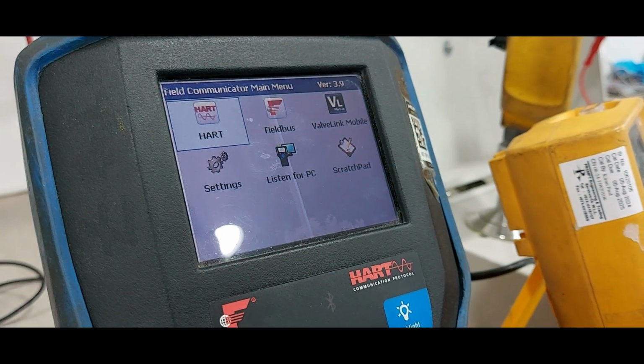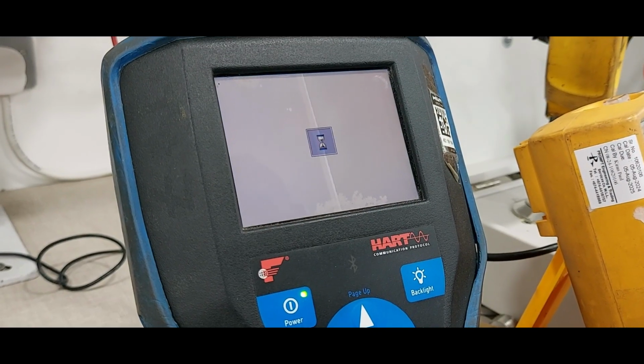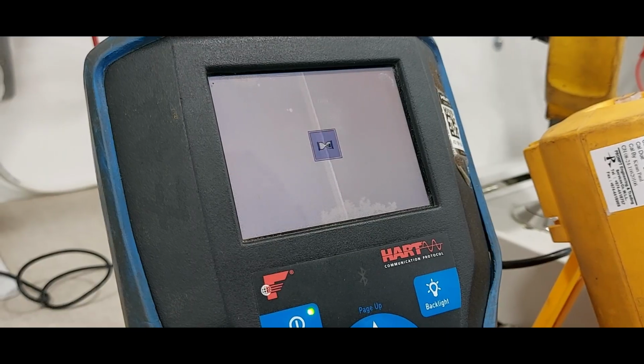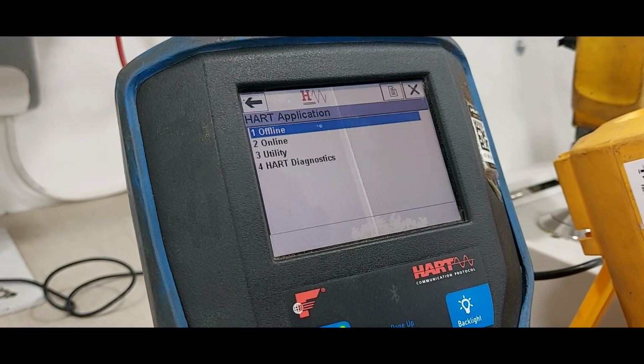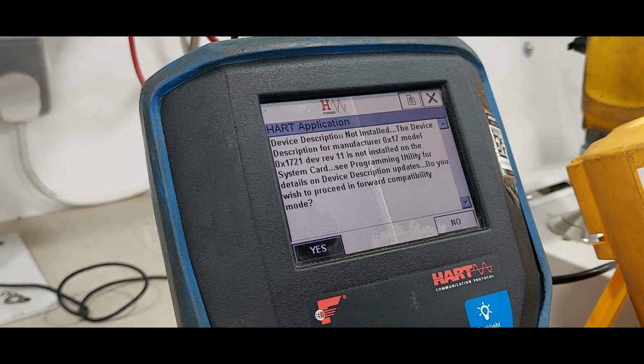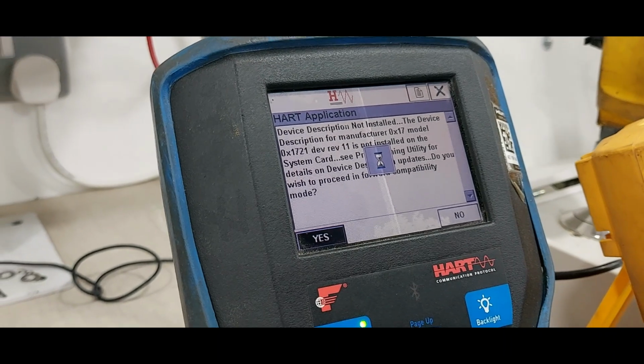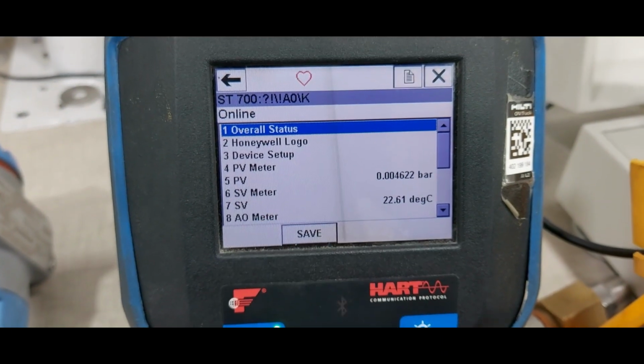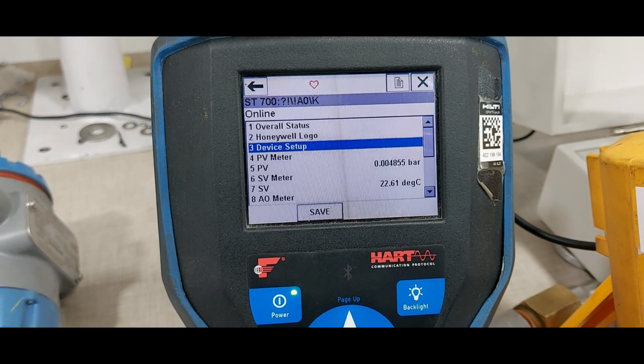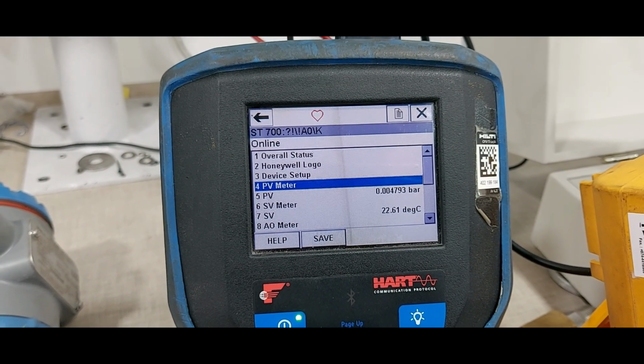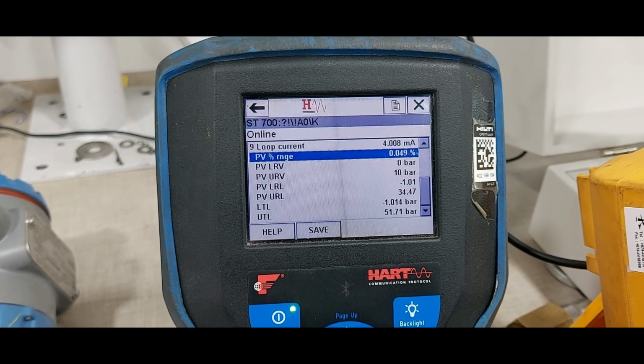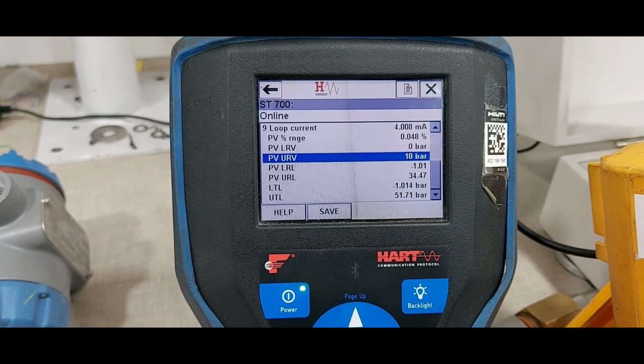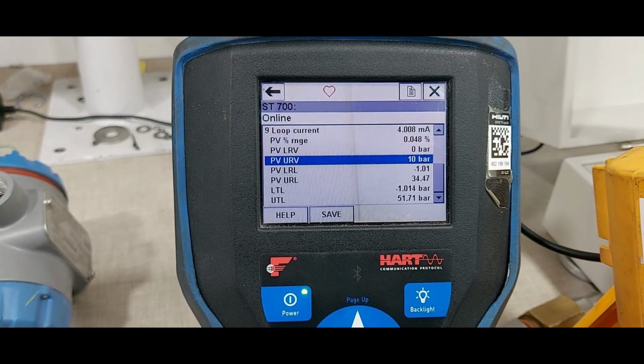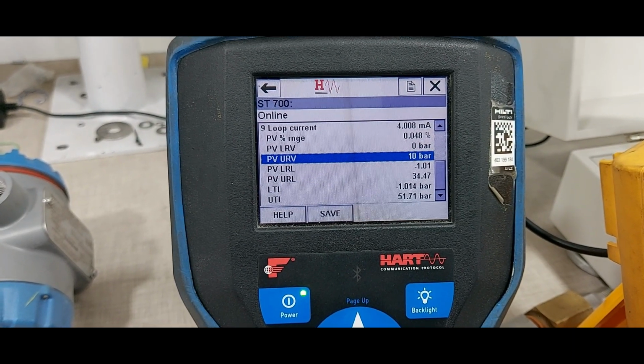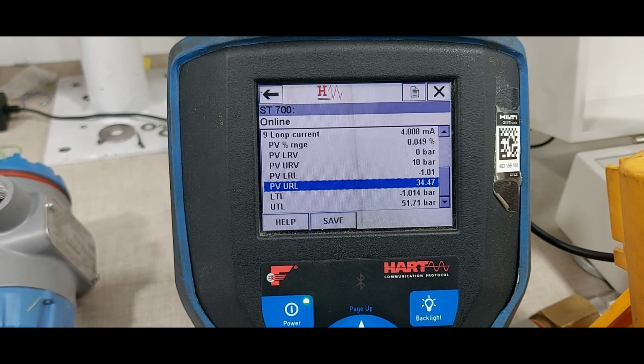Select HART function. Select. Yes. Overview status. Honeywell logo. Device setup. PV meters, PV values, secondary value, meter value, LRV, URV. URV is showing 10 bar, LRV is showing 0 bar. Upper sensor limit and lower sensor limit.